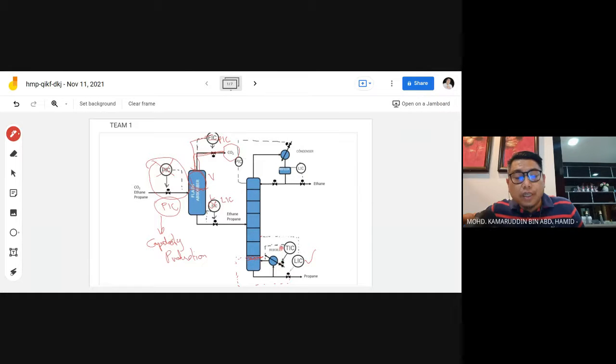All right. And since you have a distillation column, you need something at the bottom to maintain the product quality. Therefore, you need a temperature control here. Yes, this is right, but you measure the stage, not the vapor boilup stream. You need to measure any stage temperature, and then you manipulate the heating, the fuel or the steam to the reboiler. All right. So this is right.